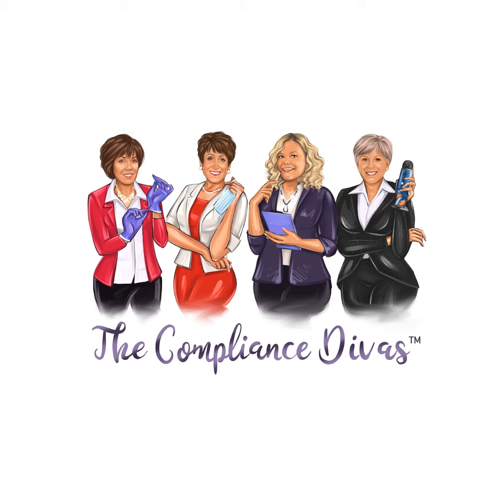This is Mary Gavoni. I'll be the moderator for this episode along with our diva, Linda Harvey. Our topic today is how do we get our instruments clean? Because it's a critical step in reprocessing and making those instruments safe for reuse. We know that all the debris needs to be removed from those instruments prior to packaging the instruments and getting them into the sterilizer. So we're going to discuss some of the important tips we have to clean the instruments, avoid having to routinely hand scrub, but making sure you get all the debris off the instruments.